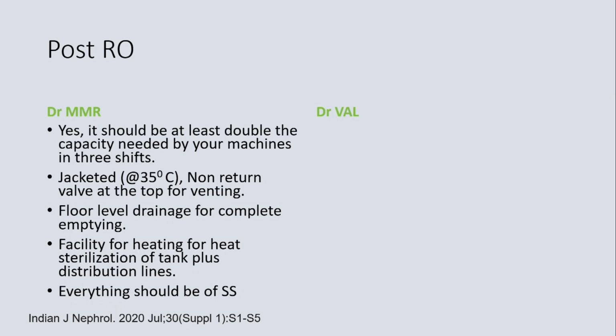So therefore your water is best kept at around 35. So what I have done is I jacketed the tank with a stainless steel jacket. The jacket itself does not need to be stainless steel, but it is glass wool covered so that you don't lose heat there. And you circulate the chill water reject from the air conditioning through the jacket to keep a temperature of about 35 degrees centigrade in the tank all the time. So it should be jacketed, to my mind. It works well because the water can then be reused for this purpose.